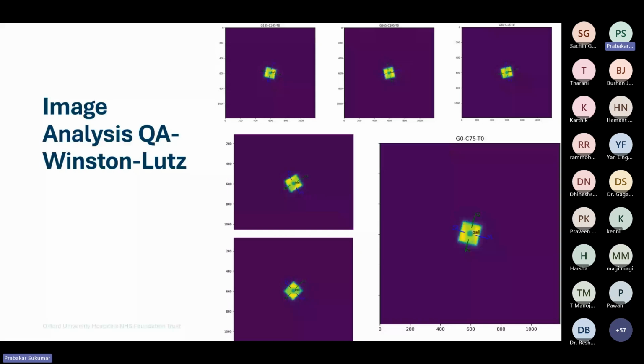So what we do is we put a ball bearing at the center of the isocenter, and then we image it at different combinations of collimator, couch, and gantry angles, and we expose that at 6 different combinations, and then we deliver that in the integrated images portal dosimetry, and we analyze it that way.